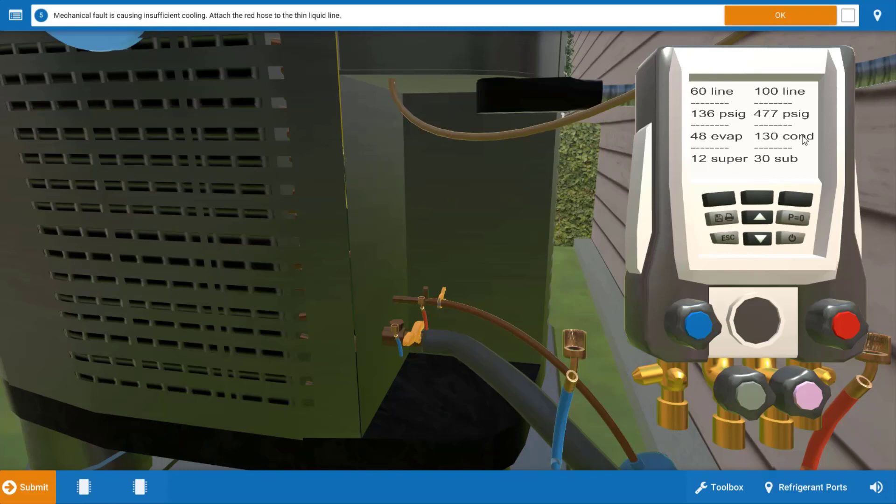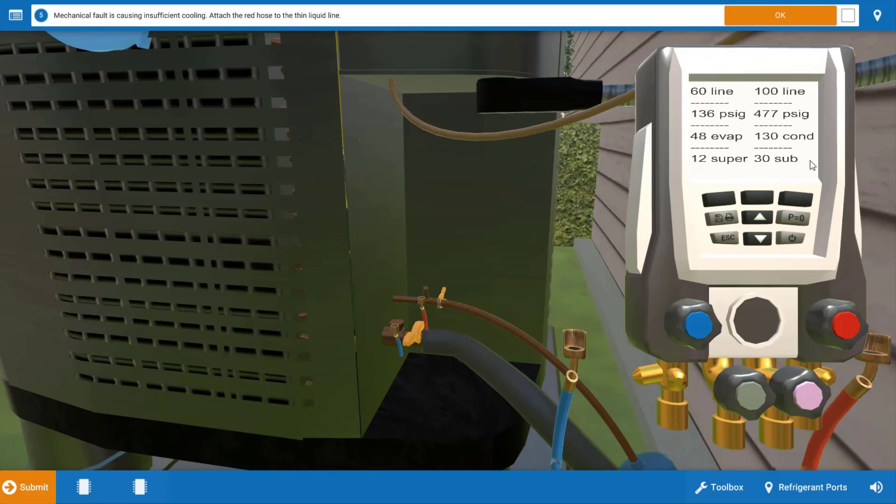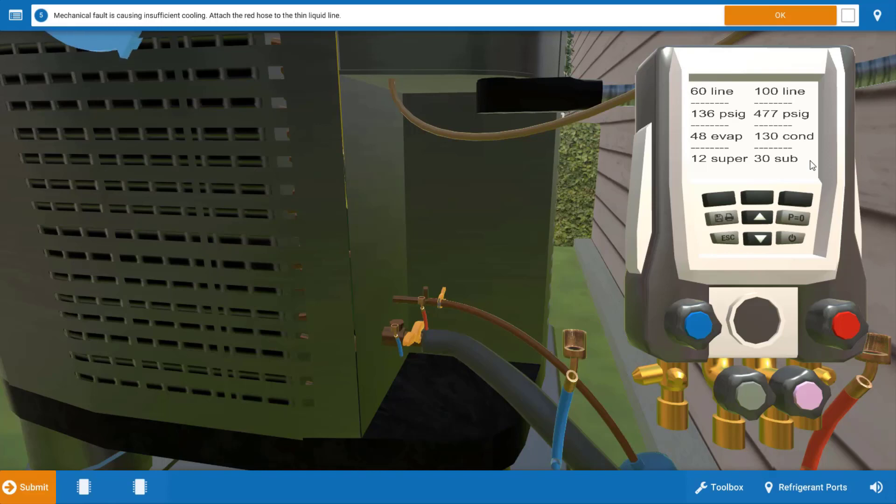If we look at our high side we have 477 PSIG which results in 130 degree condensing temperature. Under normal conditions the condensing temperature should be about 20 degrees above the outdoor ambience, so we should be around 115 there. Both of our pressures, evaporating and condensing temperature, are excessive. They're both high.